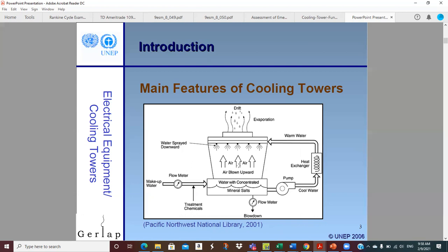And we typically have fill. Now, there are towers that don't have anything in here, but I would say 98% of the towers in the world have some kind of fill, and that's to increase the contact area between the air and the water. That's the air passing across either counterflow or cross flow, and the water's falling down. We get some evaporation going on, a small percent, and that cools the rest of it. And there could be some convective action, because this air could be 50 degrees, in which case that's going to tend to cool it down, but it also could be 100 degrees in the tower, so that could tend to heat it back up. So the tower has to operate no matter what and provide that minimum tower water temperature.